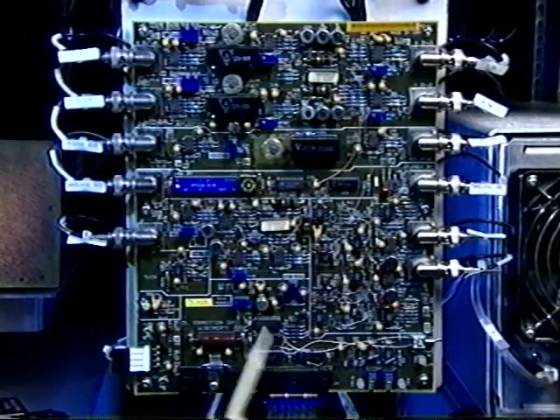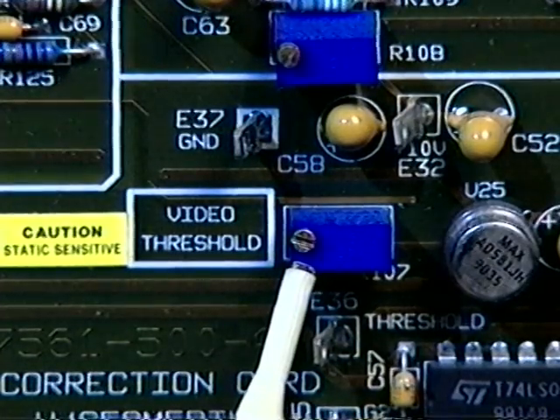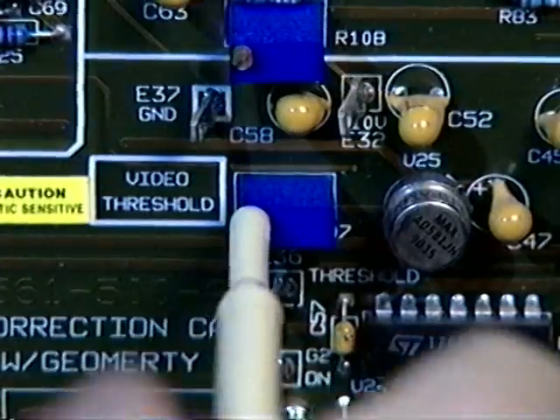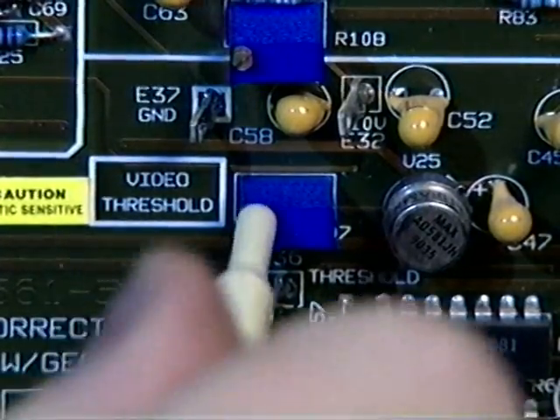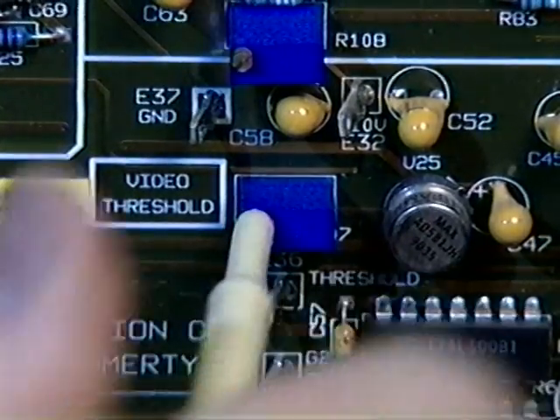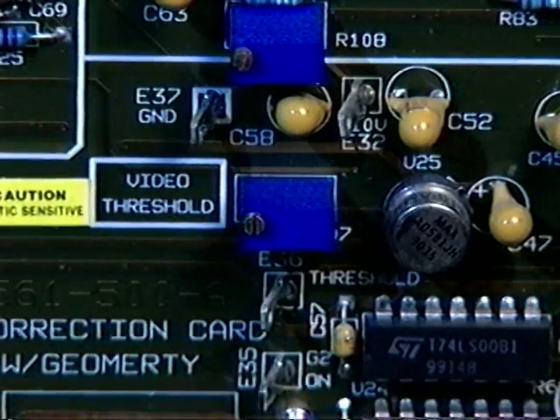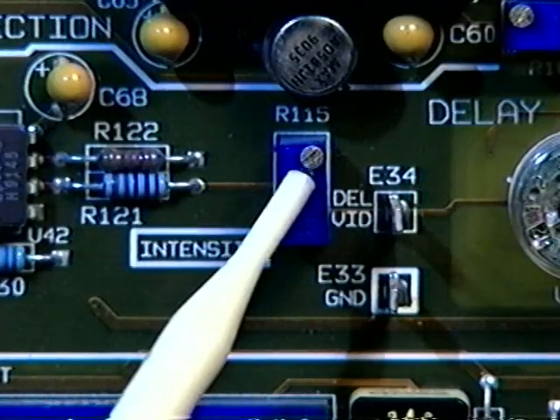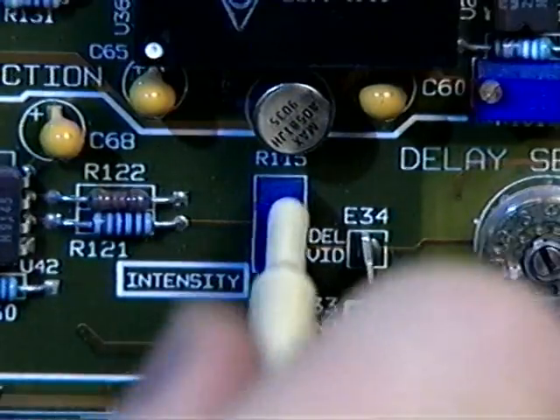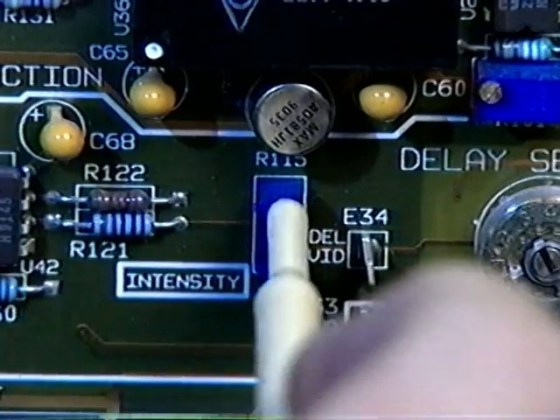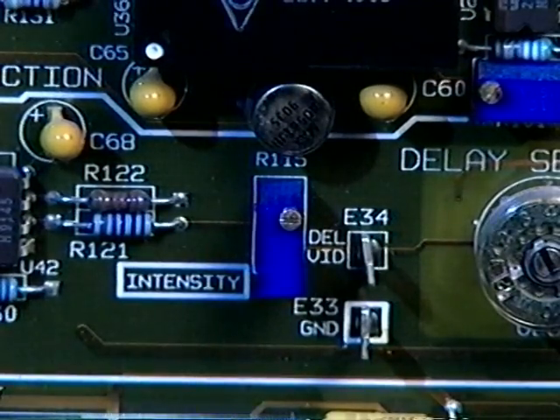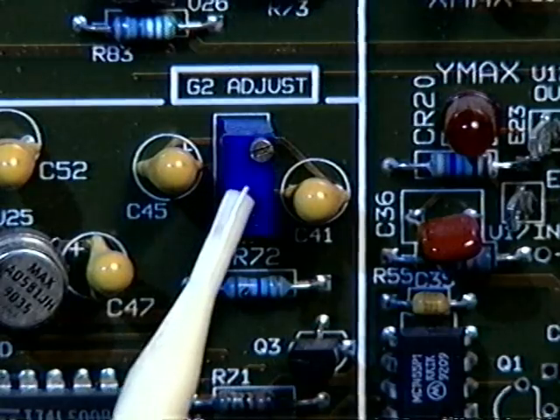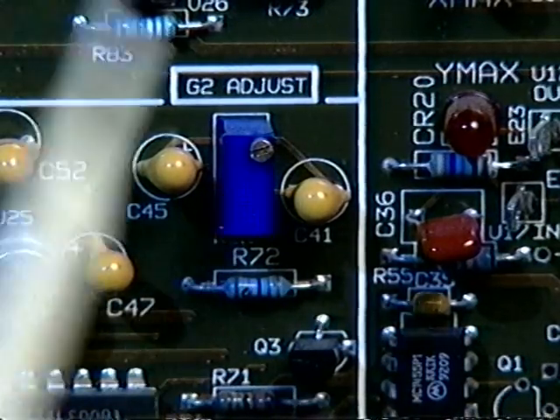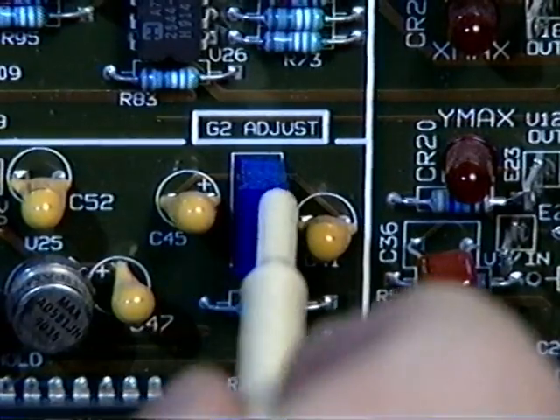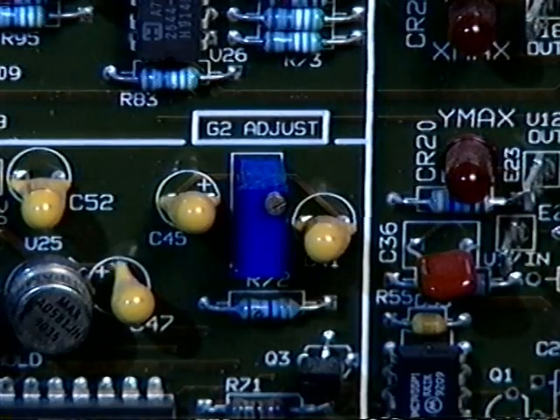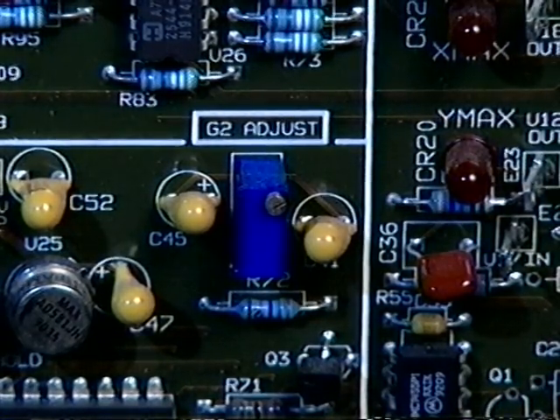Threshold. The threshold control sets the DC level for the video signal. This control sets the correct bias level for the CRT. Threshold is usually adjusted with an oscilloscope. Intensity. The intensity control sets the gain of the video amplifier. This control is always adjusted with an oscilloscope. G2. The G2 control sets the G2 voltage applied to the CRT. This control is set visually, but it is in the vicinity of 1000 volts DC.